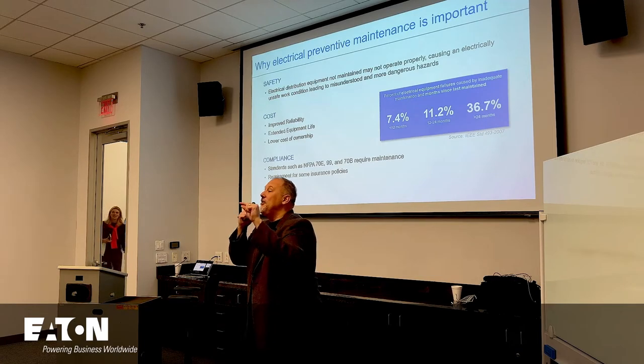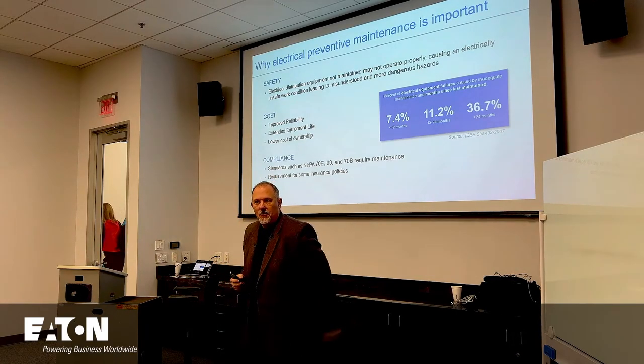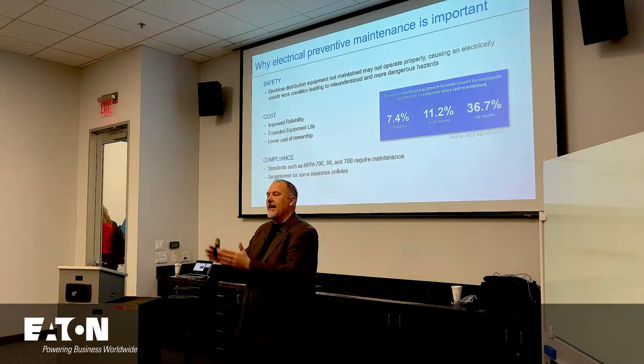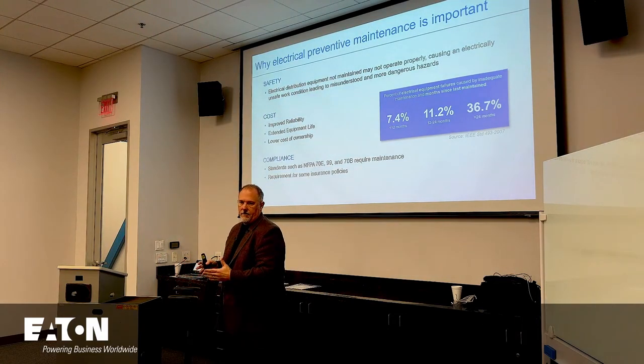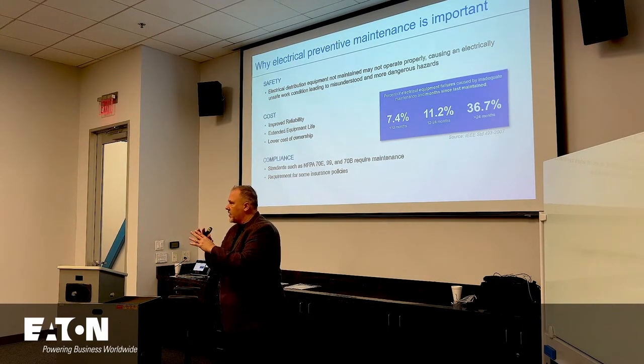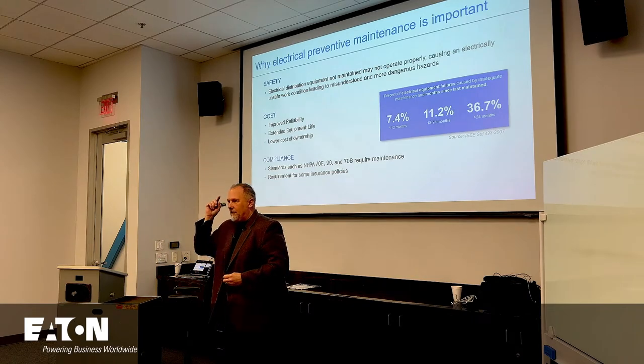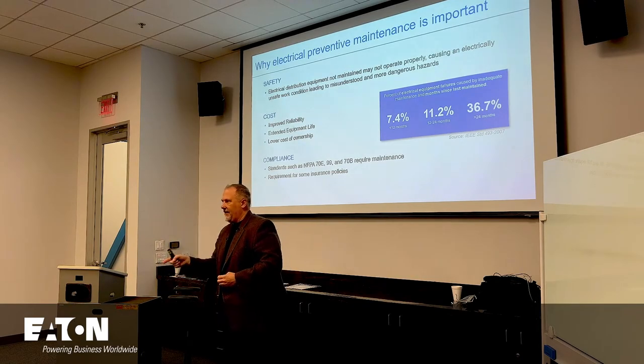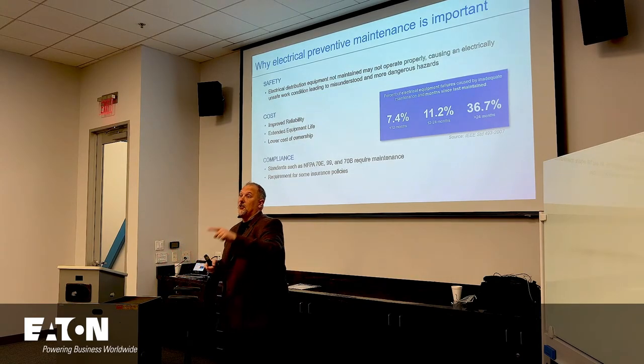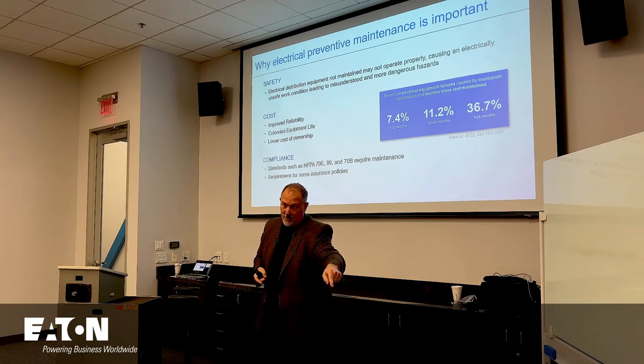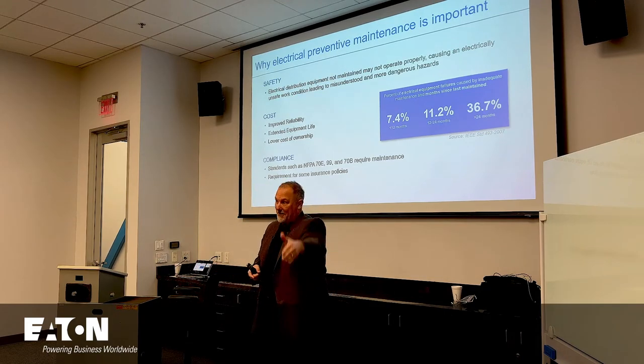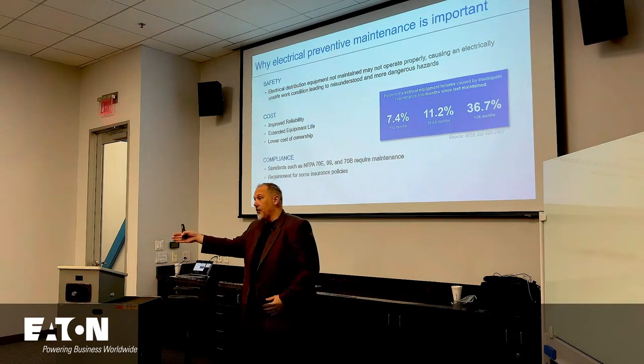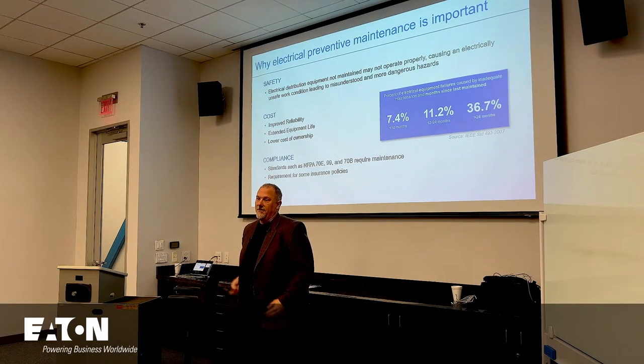He goes, I already know I have a ground fault. I said, oh, you do? He says, yes, you don't understand. I work in a salt mine. In salt, we need to explain what happens: salt builds up on the terminations, and then I get a ground fault. He says, but I don't have a budget for maintenance. I do have a budget to replace the motor and the conductors. So I want the thing to fail so that I can order a new motor and new conductors.